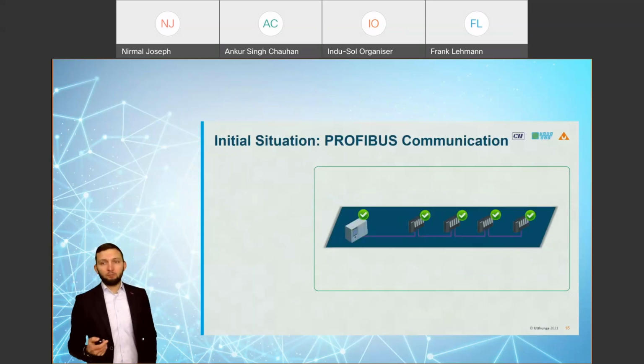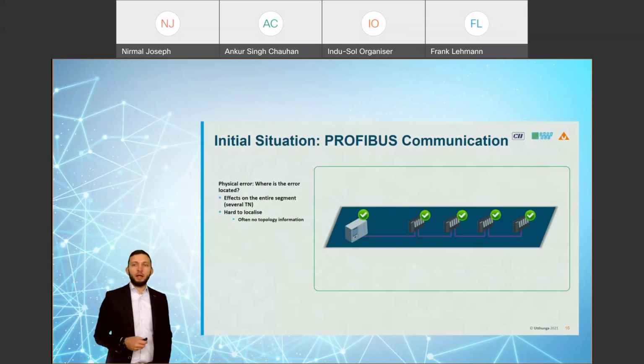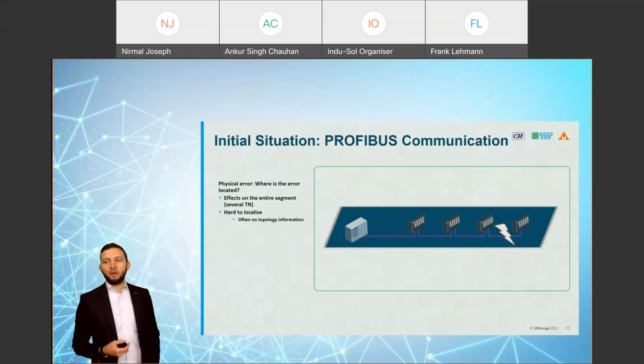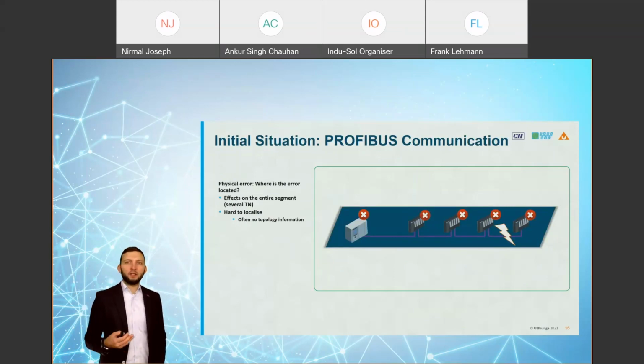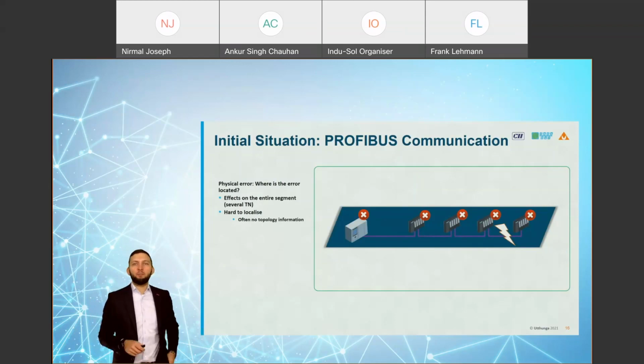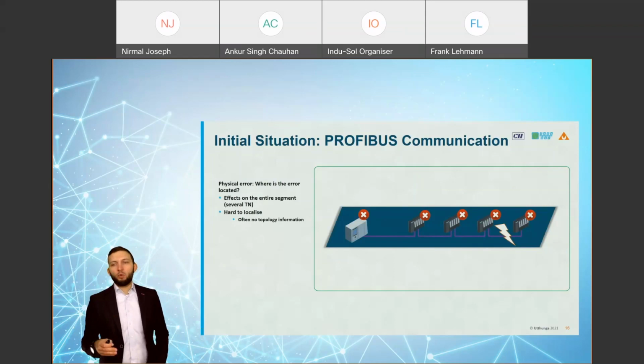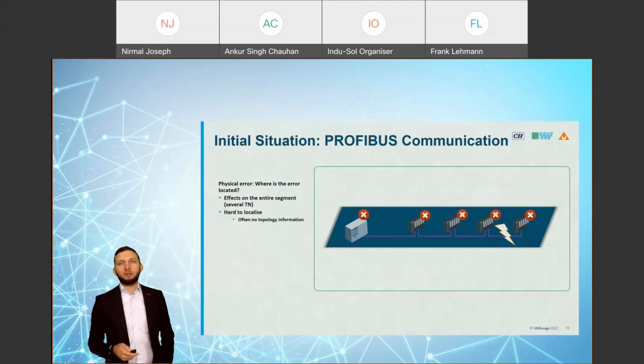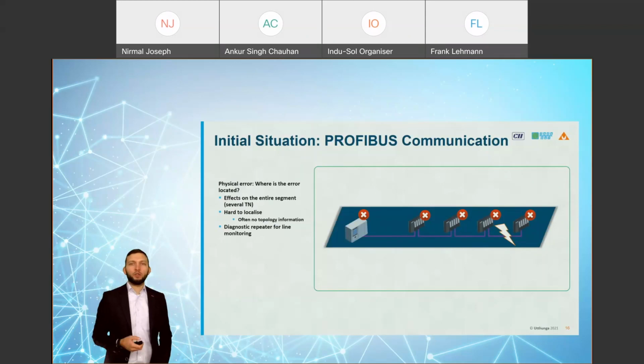So now let's go back to our Profibus communication. Now imagine I have a physical error in my network - maybe a broken line, or aging in the line, causing some impact to my communication because the line quality is not so good. In the Profibus world, it's really hard to localize this cable problem, because I have one line, terminated on both ends of the network. If I have a line or physical error, the whole communication is interrupted. Sometimes our customers or the Profibus technicians use diagnostic repeaters to detect such line problems or to monitor the line, but it's really hard to find without these tools.